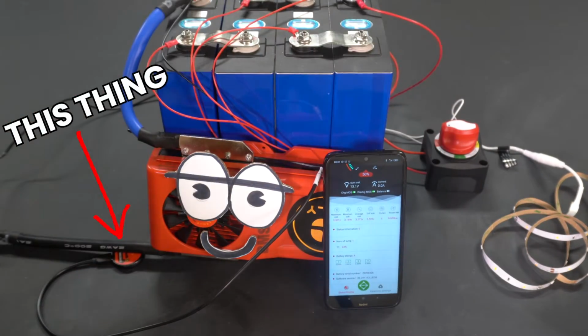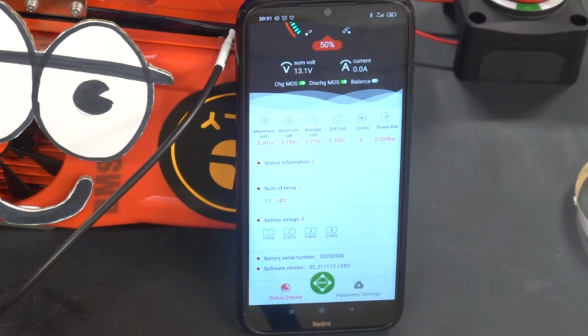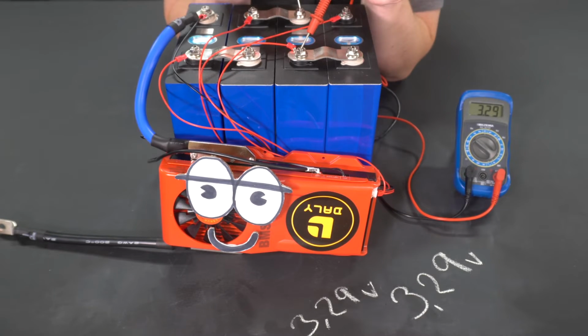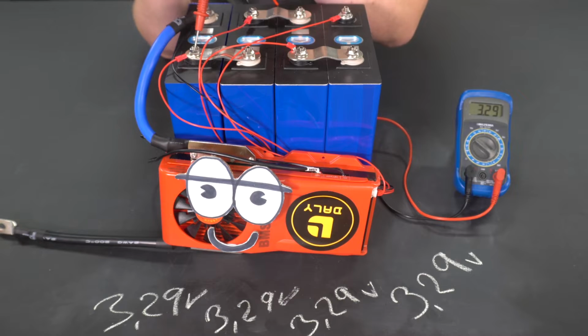But let's take a closer look at how it's actually working. This particular BMS has a Bluetooth connection, which means that we can see what's going on inside on the smartphone. We can pick up this dirt cheap multimeter, measure the individual cell voltage and confirm that we get the same measurements as the BMS. And in this case we do, which means that we wired up the BMS correctly and it's now taking good care of our lithium cells.